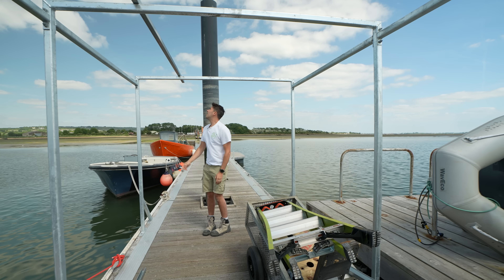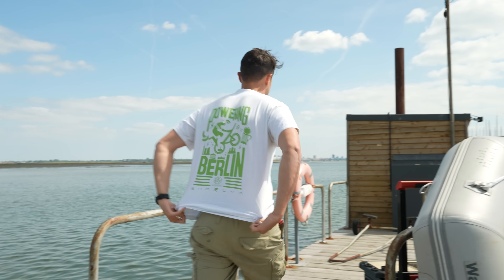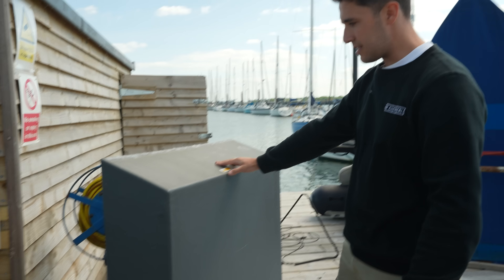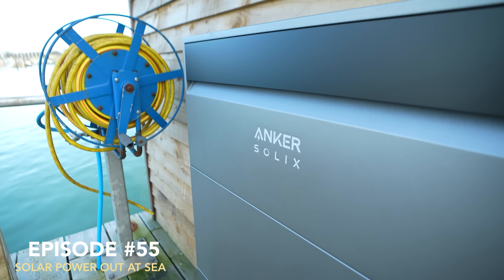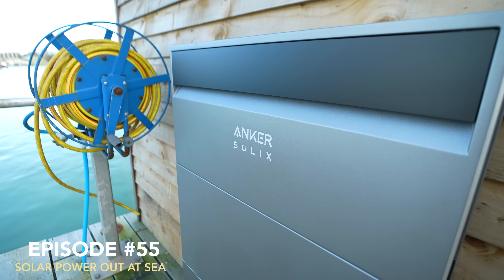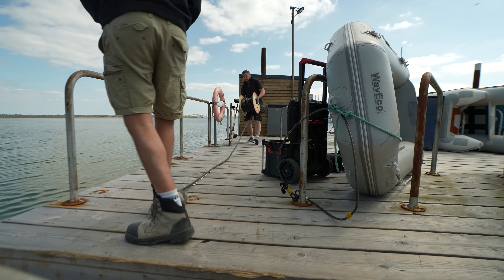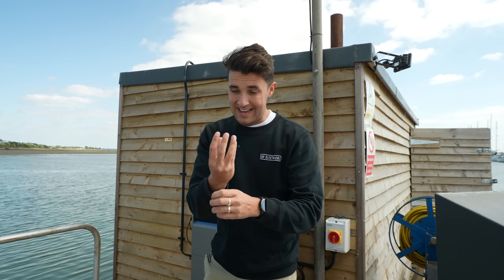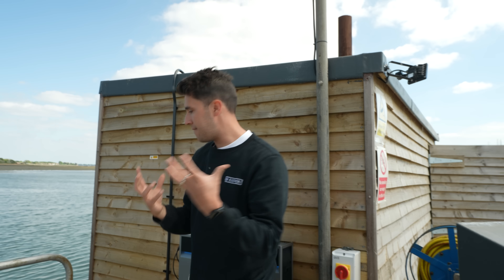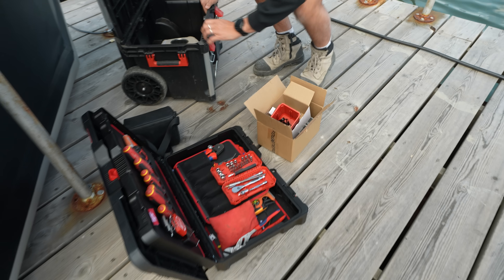There's no flexing whatsoever, though it does feel a bit wrong attaching panels to unistrut and butchering a panel clamp. This is the system we previously installed — it lives behind a custom-built insulated GRP enclosure. That's the Anker Solix X1, chosen for its corrosion resistance and ability to work off-grid, and it's been functioning absolutely beautifully far from shore. We now need to run a cable from here over to the frame. We've opted for Doncaster Cables PV Ultra cable — it's a bunch of PV cables jacketed inside another sheath, very safe and well protected — clipped along the back side of the pontoon.